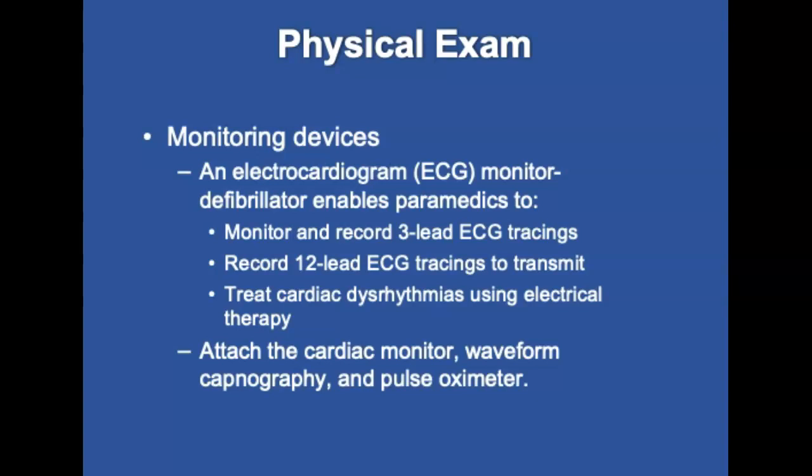An electrocardiogram, or ECG, monitor/defibrillator enables paramedics to monitor and record 3-lead ECG tracings and record and transmit 12-lead ECGs to the receiving facility. An ECG enables paramedics to quickly identify suspected AMIs and make sound transport decisions. The device also gives prehospital providers the ability to treat cardiac dysrhythmias using electrical therapy such as defibrillation, synchronized cardioversion, and transcutaneous pacing. Attach the cardiac monitor, waveform capnography, and pulse oximetry when obtaining vital signs.